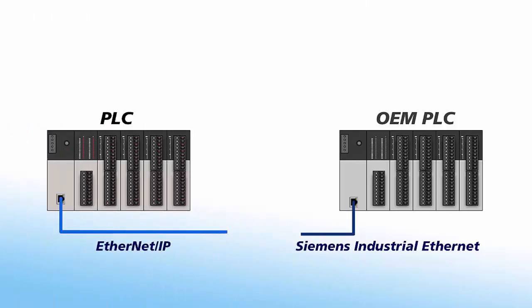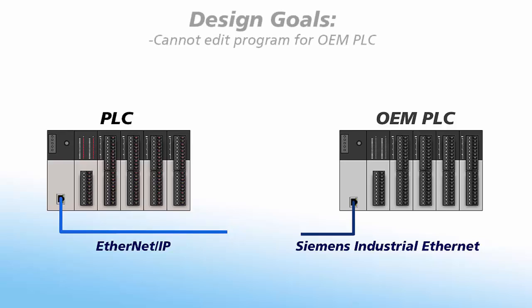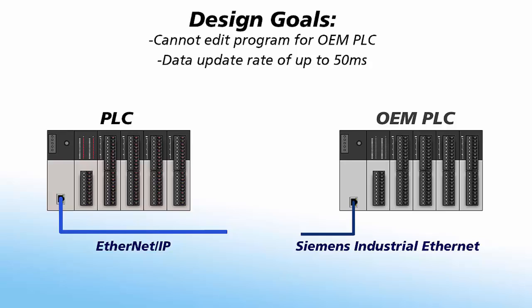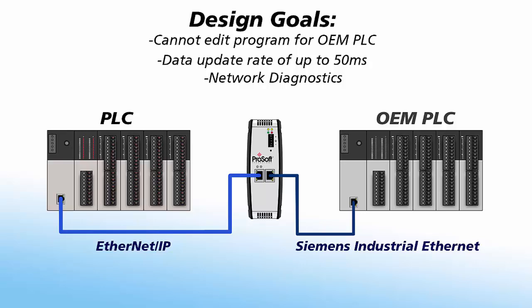For our next example, we'll take a look at a PLC that talks EtherNet/IP that needs to communicate with an OEM's PLC that talks Siemens Industrial Ethernet. In this example, we do not want to edit the program on the OEM PLC. We'll need fast data transfer of no slower than 50 milliseconds and be able to diagnose communication problems using the EtherNet/IP PLC programming software or an HMI communicating with it. Editing the program in an OEM's PLC to initiate data transfers could void the warranty, performance guarantees, or you may not have access to the programming software. Therefore, for this example, we will use our gateway as a client on Siemens Industrial Ethernet in order to communicate with the OEM PLC acting as a server.